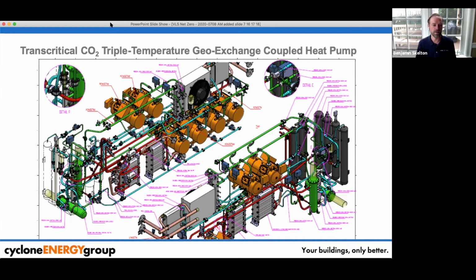The triple temperature design means we wanted to find a way to reduce loads. With refrigeration, like any store with refrigerators, a grocery store or a Walgreens, we have 50 feet of cooling and freezer cabinets in this store, and those typically have a gas cooler that takes the refrigerant outside and releases heat energy, 24 hours a day, 7 days a week. We felt we needed to capture that energy somehow, since we have a long heating season in the Chicago area, so we wanted to capture and reuse it. The only way we could figure out to do some kind of heat exchange was to put it into the ground and use it through the geo-exchange system.